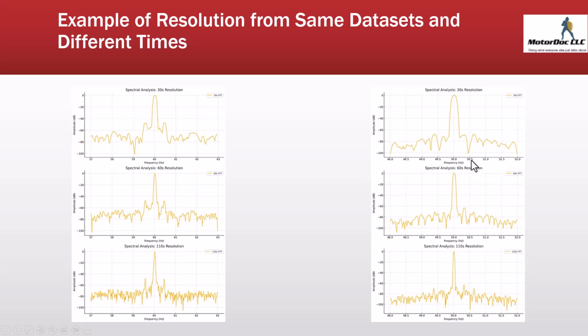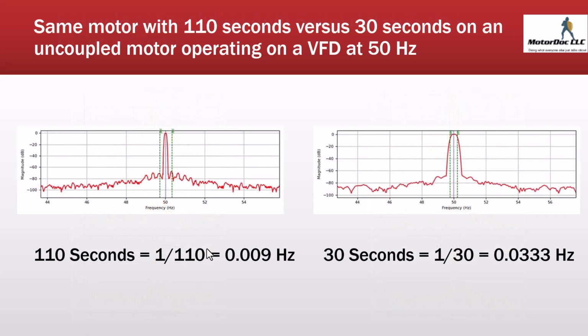And this is the same thing again with a defect that didn't exist, and then poof, there's the unloaded machine. There's some pole pass right there. Same type of thing here. It's in tight, and pole pass definitely sticks out, but other signatures go away. They basically fall back into the noise. So you see this peak here. Well, it didn't really exist. This is the same data set, just evaluated at different times. So let's say 110 seconds at 0.009 hertz, there's a pole pass frequency, and under the exact same set of data looked at in 30 seconds, you can see the pole pass frequencies blend in with the line frequency. This results in either a false positive or false negative.